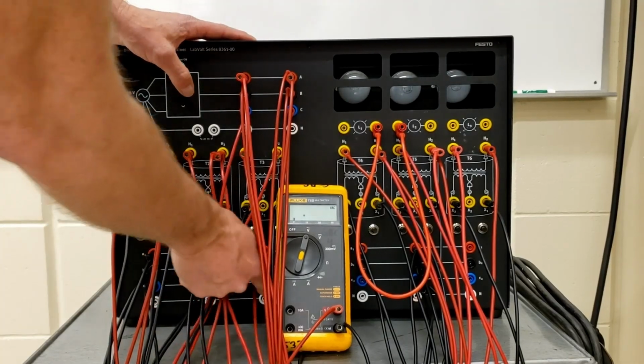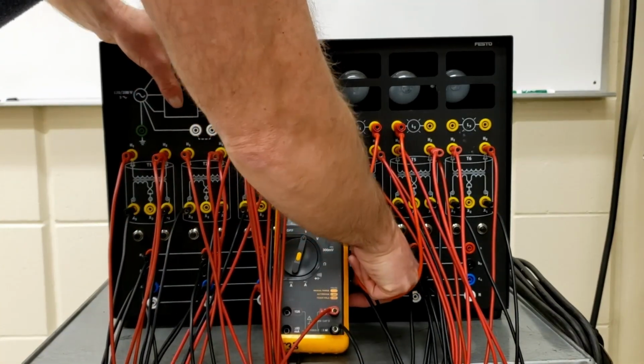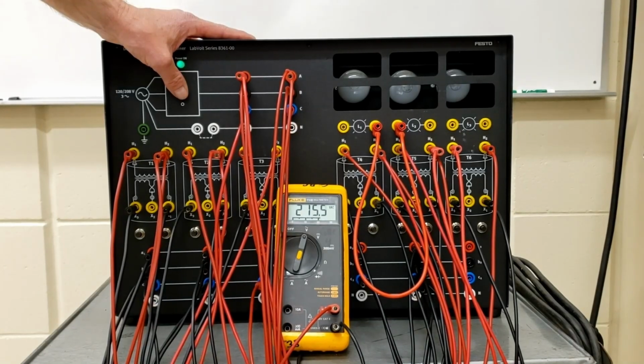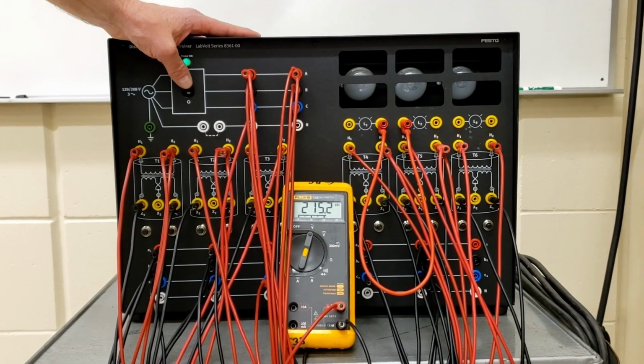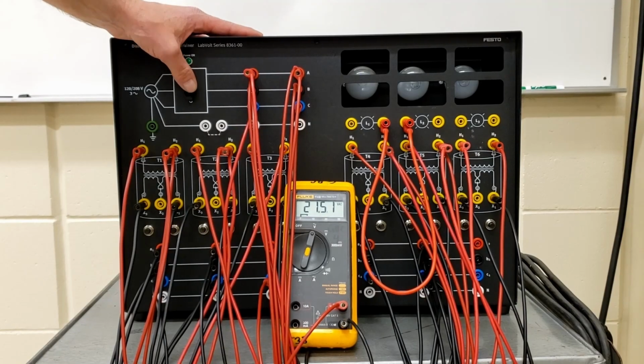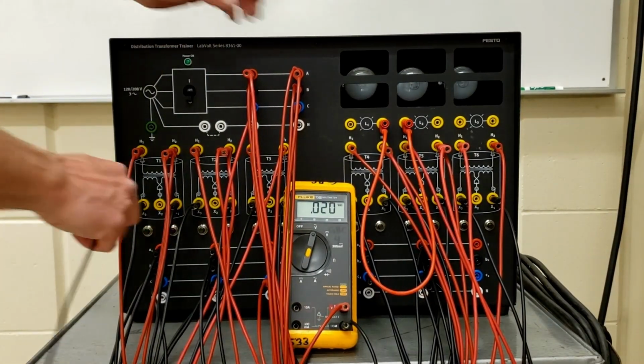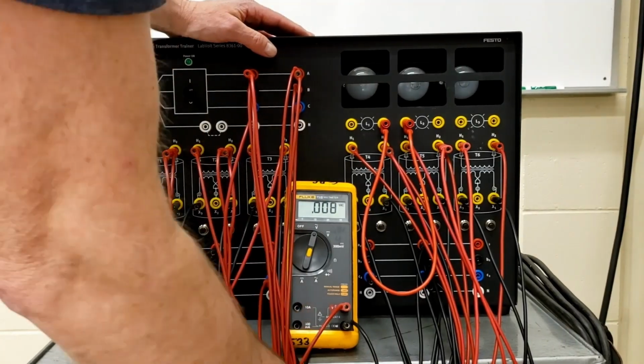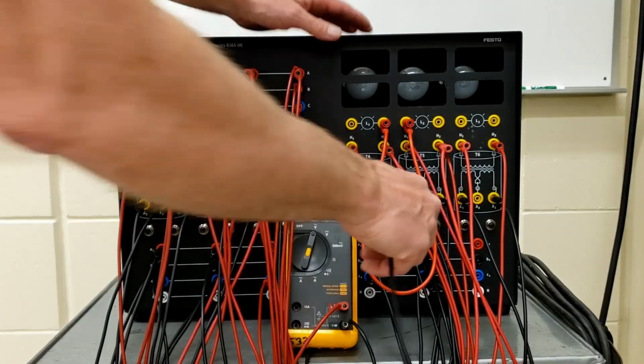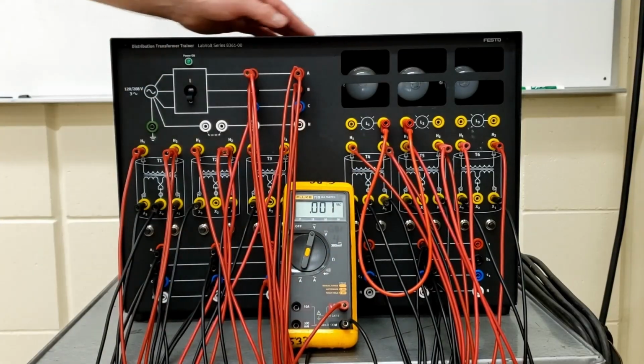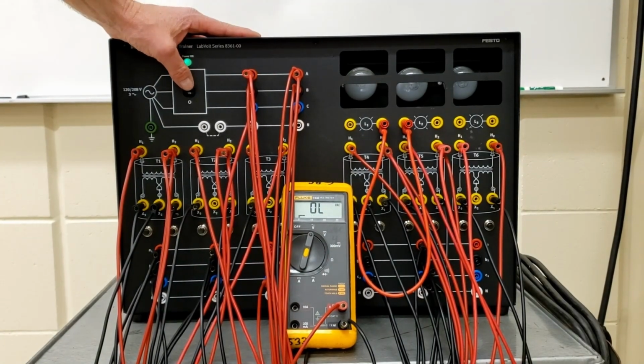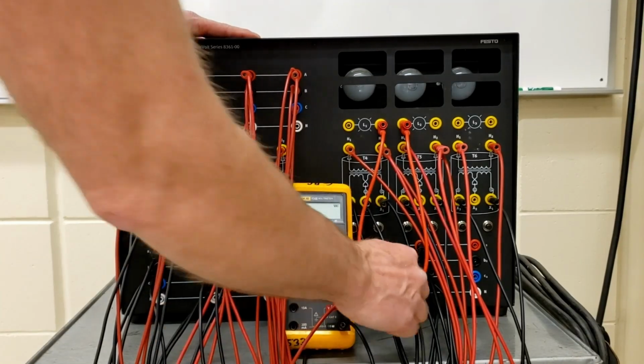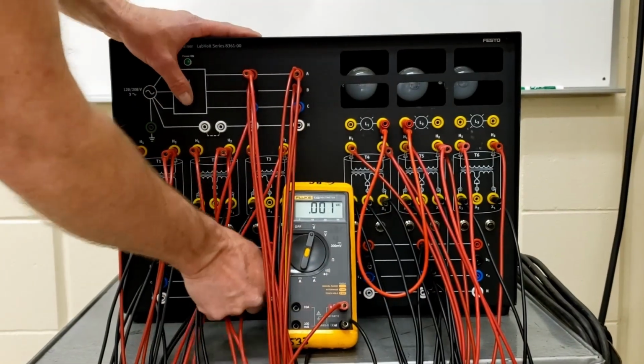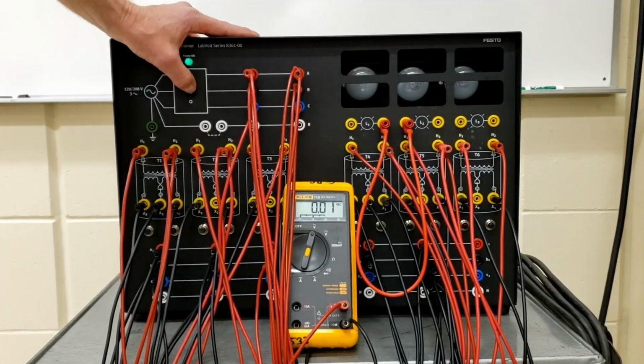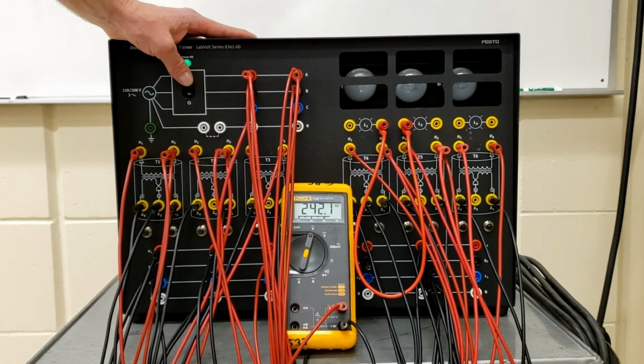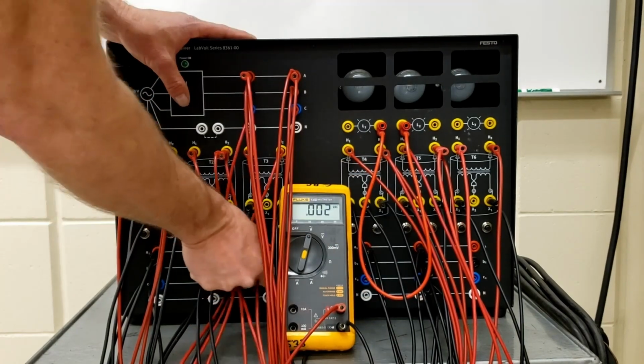225 on the B, and 215 on the C. That's without either transformer being grounded, or without them having a reference between them. So if we bring the X2s of the first transformer and ground them, then they both have a reference that is tied together. At that point, I've got 416 on the C phase, and my B and A go to 240. 240 there, and 240 on this guy.